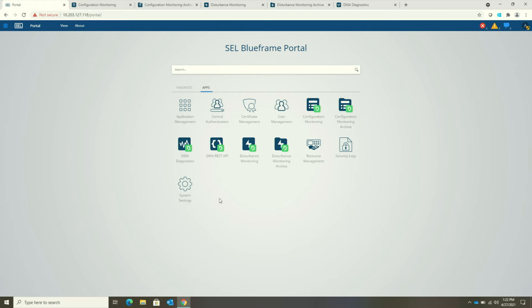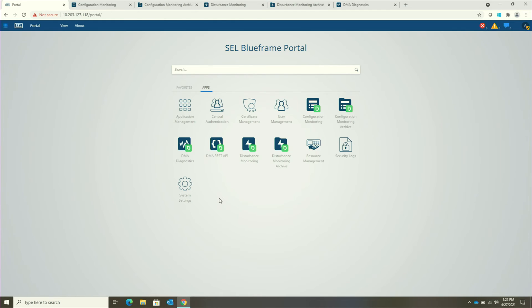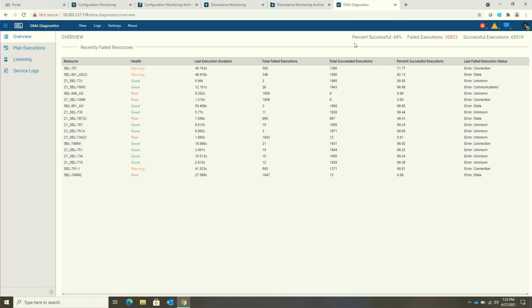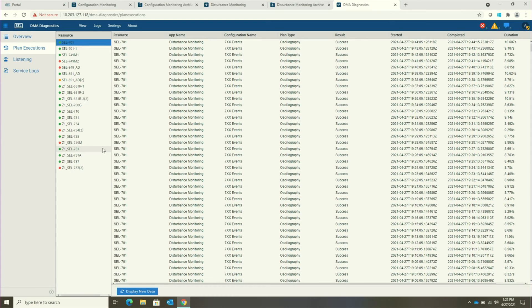The next supported tool is DMA Diagnostics. DMA Diagnostics is the automation system troubleshooting tool that helps users analyze how their automated system is running. We understand that the communication networks in power systems are very sophisticated and intricate, and because of that they're likely to encounter some failures over time. Having DMA Diagnostics provides holistic system overview statistics so you can understand how the automation system is working as a whole, as well as the ability to dive down into specific device-by-device interactions to understand successes and potential failures so you can troubleshoot your system.